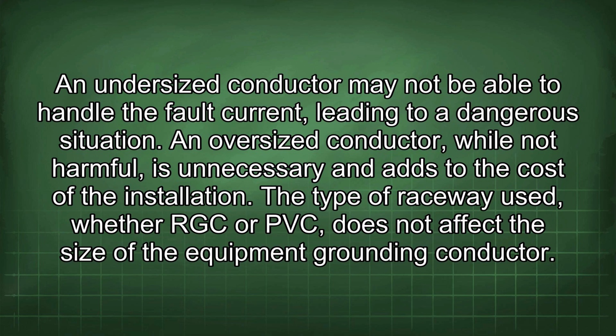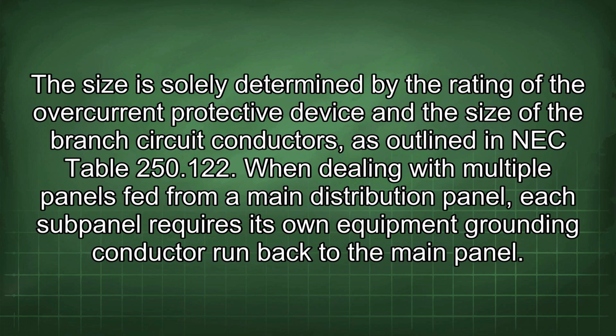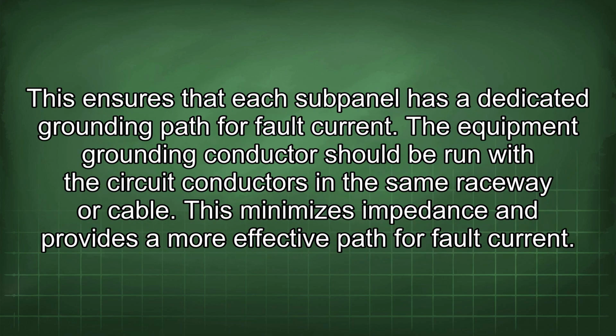An oversized conductor, while not harmful, is unnecessary and adds to the cost of the installation. The type of raceway used, whether RGC or PVC, does not affect the size of the equipment grounding conductor. The size is solely determined by the rating of the overcurrent protective device and the size of the branch circuit conductors, as outlined in NEC Table 250.122. When dealing with multiple panels fed from a main distribution panel, each subpanel requires its own equipment grounding conductor run back to the main panel. This ensures that each subpanel has a dedicated grounding path for fault current.